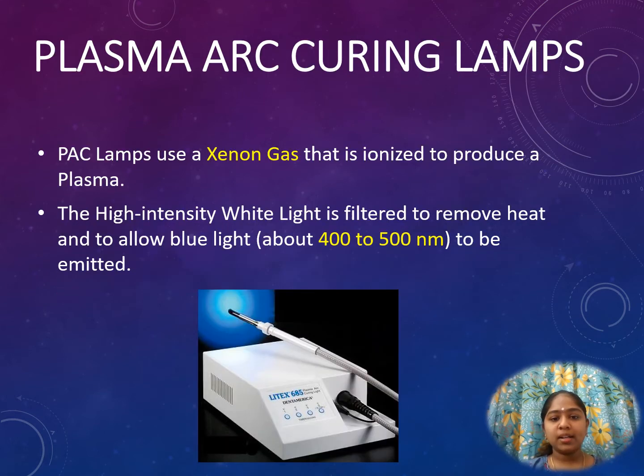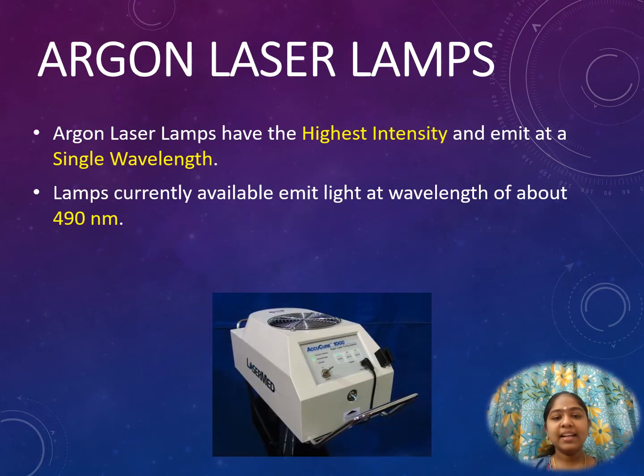Plasma arc curing lamps, or PAC lamps, use xenon gas that is ionized to produce a plasma. The high intensity white light is filtered to remove heat and to allow blue light, about 400 to 500 nanometers, to be emitted. Argon laser lamps have the highest intensity and emit a single wavelength. Lamps currently available emit light at a wavelength of about 490 nanometers.